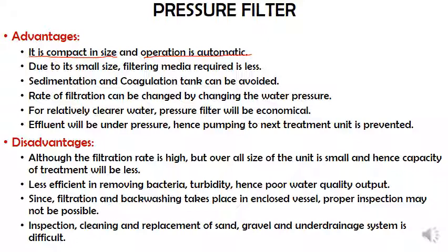Due to its small size, the filtering media required is less. When you compare it with the previous two units, that is a slow sand filter and rapid gravity filter, the amount of filtering media required here is very little because the size is small. Sedimentation and coagulation tank can be avoided. If it is relatively clear water, then we can skip this sedimentation and coagulation tank, and directly feed it into the pressure filter.